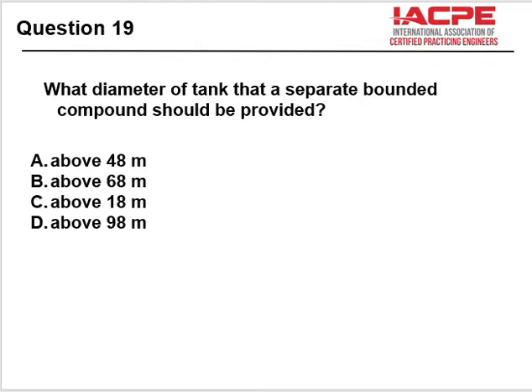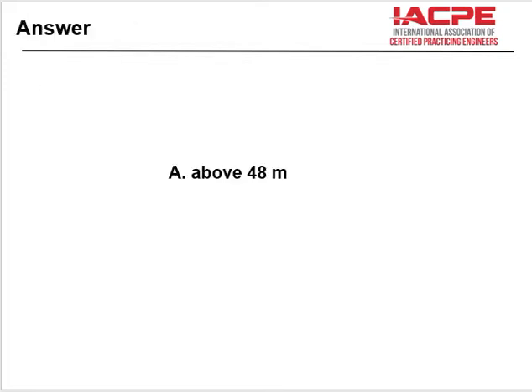What diameter is a tank that a separate bounded compound should be provided for? Sometimes you can put multiple tanks in one compound, but if it's above a certain size, it has to have its individual diked area, and it's above 48 meters.